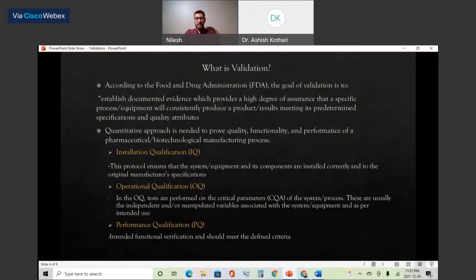In operational qualification, OQ, the machine has many functional parameters. You can use multiple approaches, but you have to decide based on what is mentioned in the URS. For example, if you said my machine should operate at 120 speed or 120 degree temperature, then you should qualify the machine at 120.